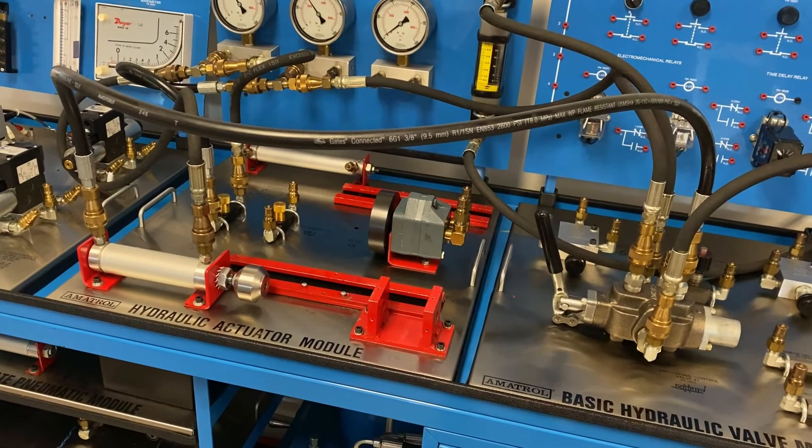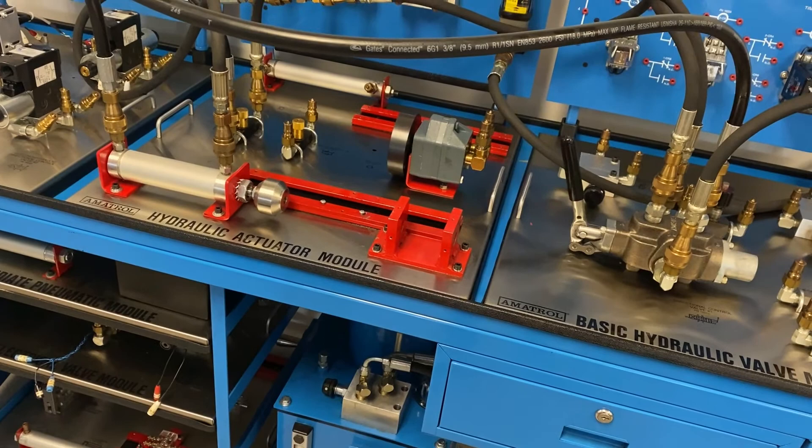So, again, the only difference between these two concepts is one is called meter-in. We're metering the fluid that goes into the cylinder. The second concept that I just showed you, we call that meter-out. In that case, we're only metering the outflow of the fluid. Okay guys, I think that finally does it for me on this video. Once again, thanks for watching.